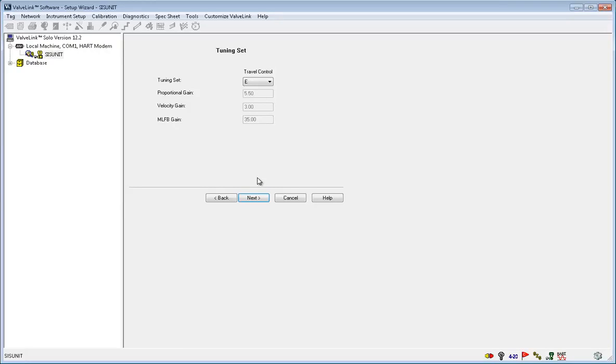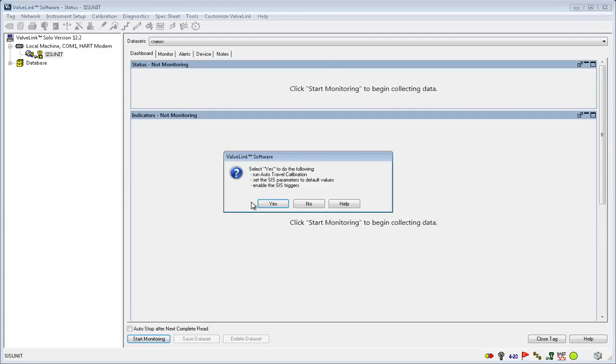Now choose your tuning set. A tuning set is selected based on the actuator type and size selected previously. My tuning set is E. Choose your tuning set and then click Next to proceed. If this is the first time you're running the Setup Wizard, you can choose Yes, but if your instrument may have previous settings, you'll lose them if you pick Yes. Click Finish. At this point, your options have been configured.